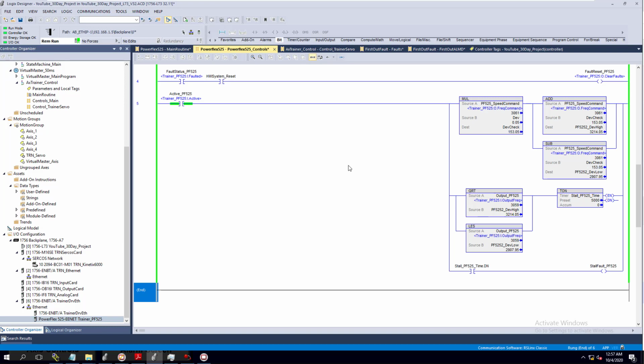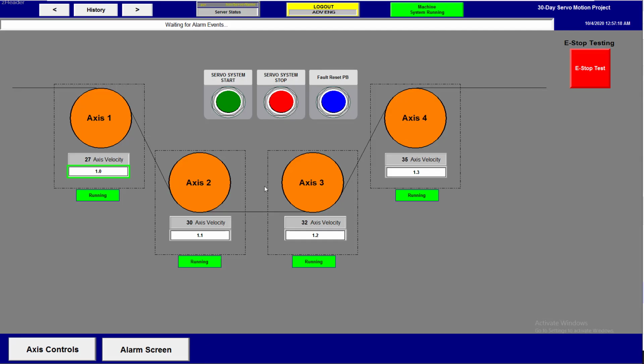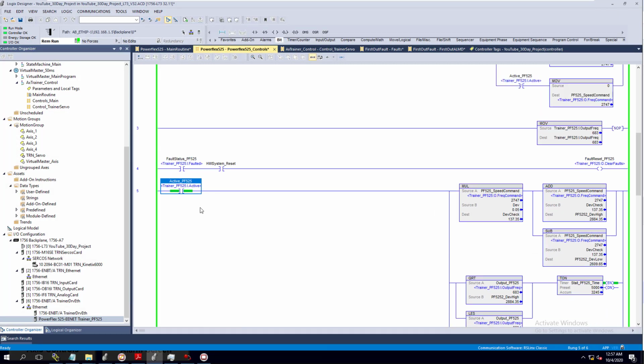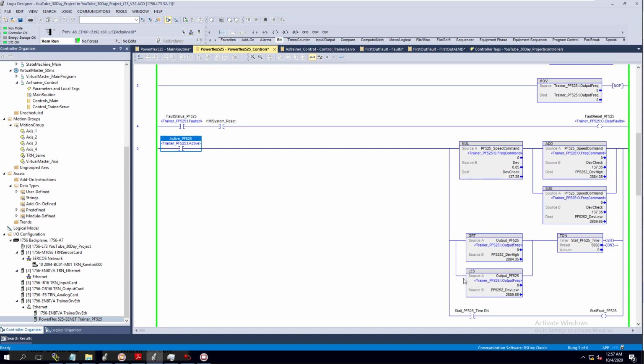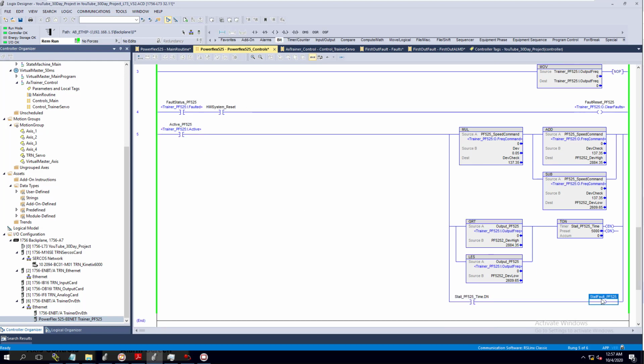And it's just checking the deviation on that, right? So all we're doing is basically saying, okay, the motor's doing what it's supposed to. So at any given time it stalls out past 5 seconds, we want to fault out. Okay, so with that understanding, we'll stop the system. We're still monitoring on the active, so it still will monitor the active during a slowdown, during a ramp down, right? So if it is faulted, if it does stall, then we want to stop.